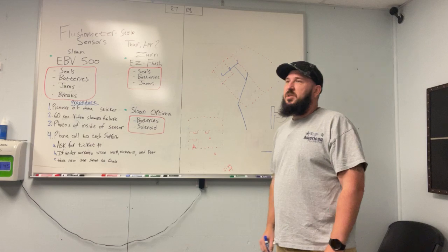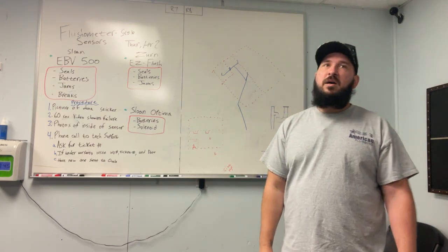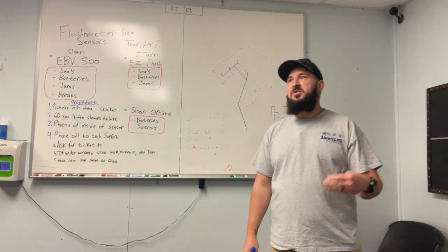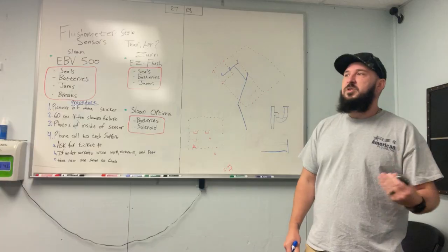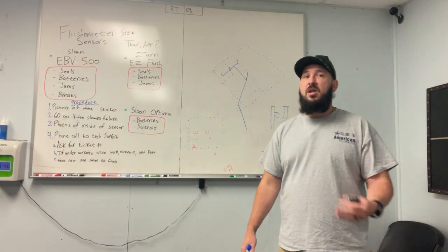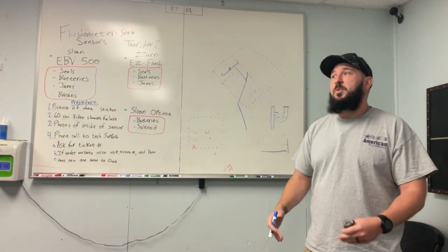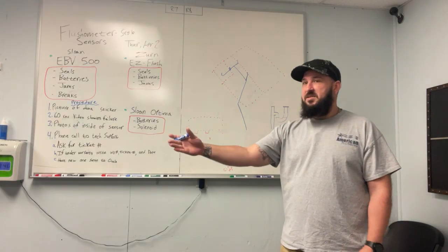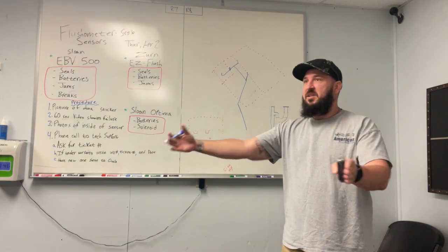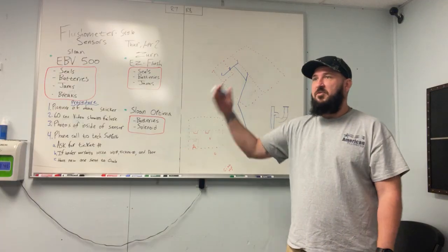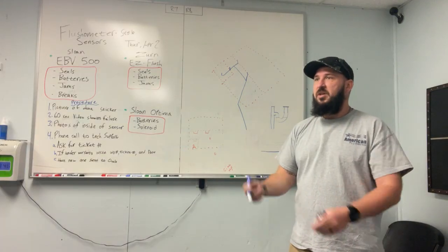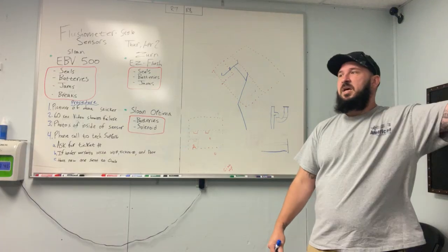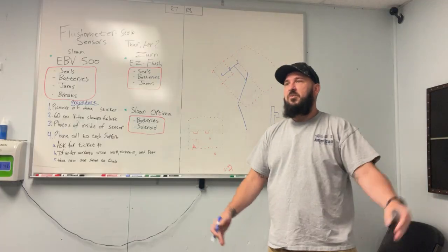And that's why there's a lot of codes. When your vent stack exhausts above the roof, it has to be so many feet from a window, so many feet from an AC return. There's a lot of times where the store always smells like poop, and you do a smoke test and can't find anything. You go on the roof, the AC is here, the vent stack's here. The AC sucks the smell right into it, and now you have cold poop smell blowing through. So you just have to offset the vent so many feet away so it expels away from it, and it'll fix it.